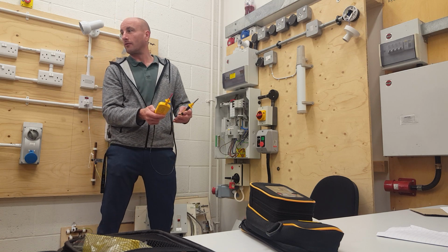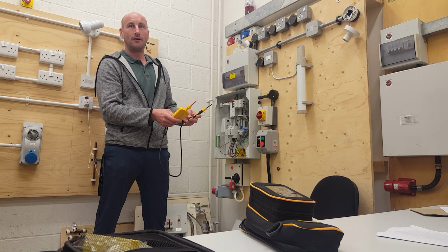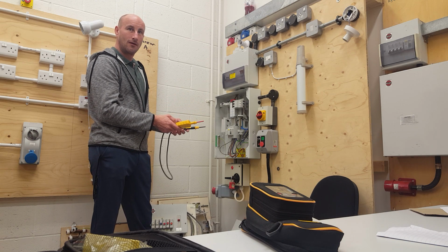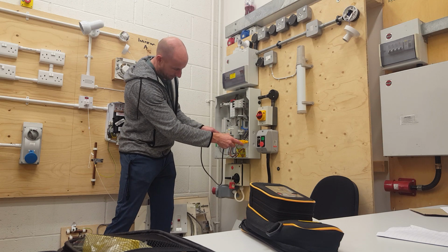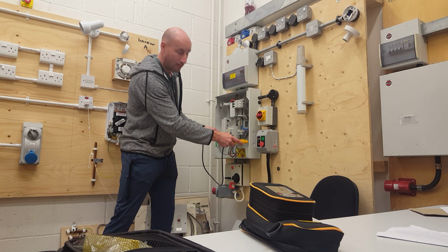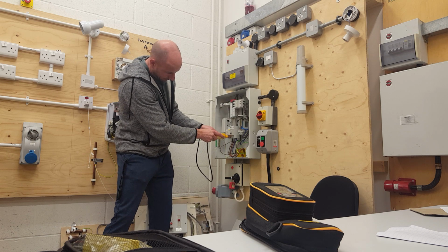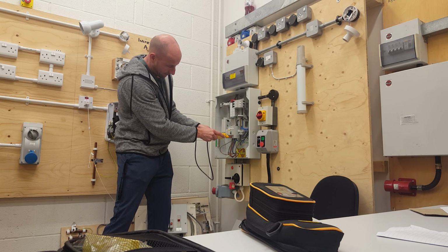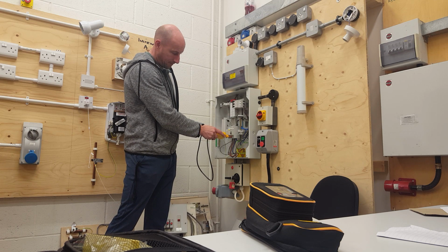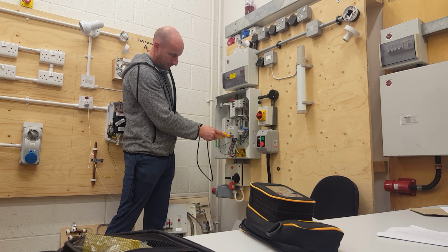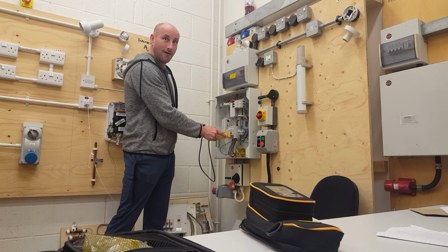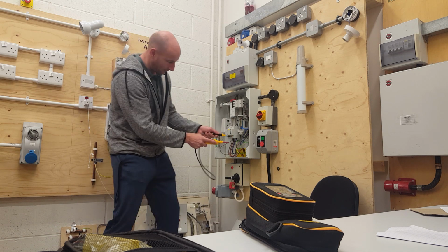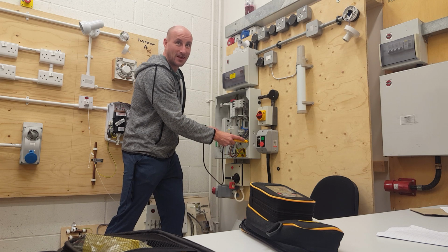Who would like to go through them? Who reckons they can do it? Go on then, Josh. L1 to earth, yep, L2 to earth, yep, L3 to earth, yep. L1 to L2, L1 to L3, L2 to L3, and L1 to neutral, L2 to neutral, L3 to neutral, that's 9. Oh yeah, neutral to Earth. Everyone forgets that one. Yeah, neutral to Earth. That's our 10 tests done, yeah?